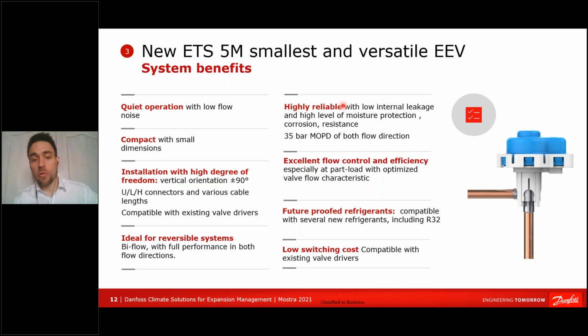You will see on the drawing on the next slide that it can come in several configurations that make it very suitable for designing all kinds of different applications. It works obviously in biflow with the same characteristic in both directions, and something quite nice when you start discussing the regulation and the algorithm you have to develop to control the valve: it has a linear flow characteristic, meaning you have a linear trend between the mass flow through the valve and the opening degree of the valve. This can be quite nice when you start to work with PID and that kind of thing. It makes the regulation work much easier.